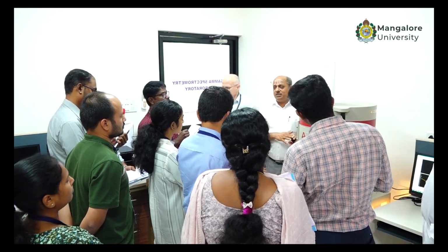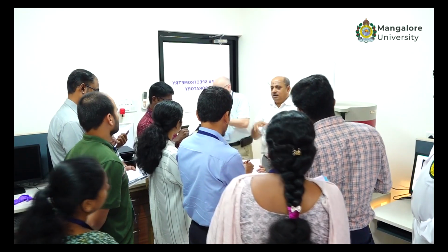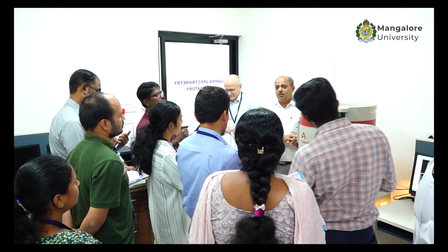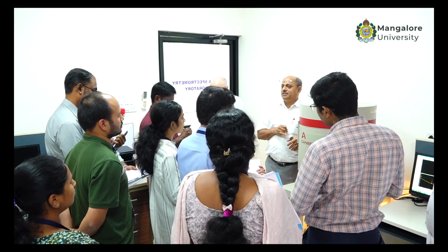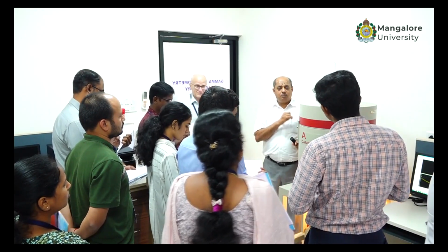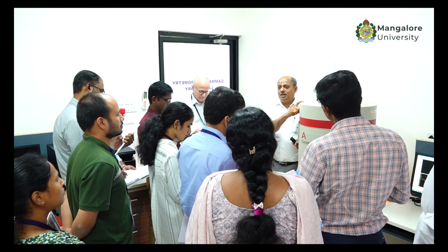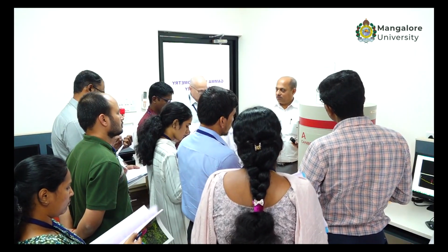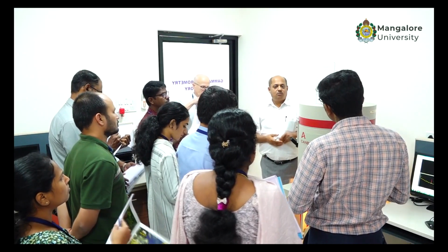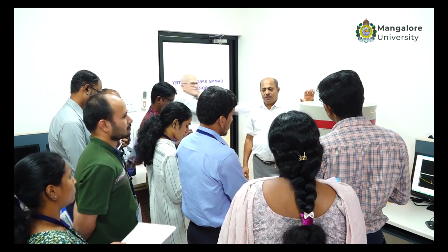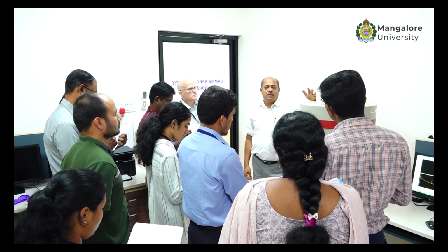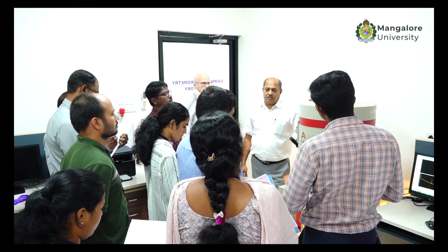Nominal means among a group of detectors, if you measure the efficiency, what is it? That's it. So efficiency is one parameter which characterizes the detector, an important parameter. The second one is the minimum detection level. Of course, you will be calculating the minimum detection level for each of these detectors. That is, what is the minimum level of a gamma active radionuclide you can detect with this detector. That is another parameter.